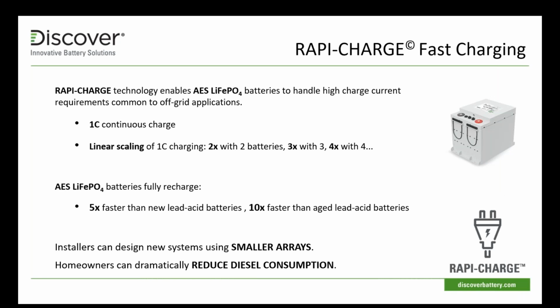That also is a support for what we call RAPI-CHARGE, which is the capability of fast charging this. So the Discover AES battery can accept a continuous charge of 1C. That's the full rate. So the 6.65 kilowatt-hour battery is 130 amp hours at 51 volts. So you could put 130 amps into the product at 51 volts, no problem. It will accept that. That is extremely high and extremely fast recharging. It's one of the significant advantages of our battery, its ability to charge very, very fast.